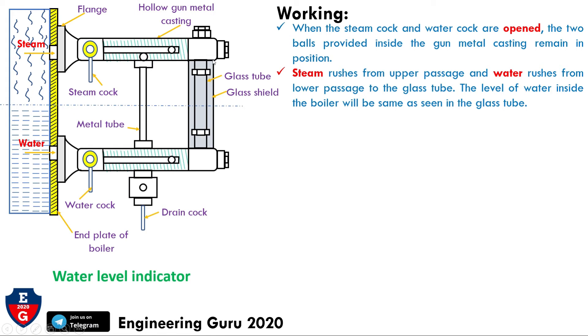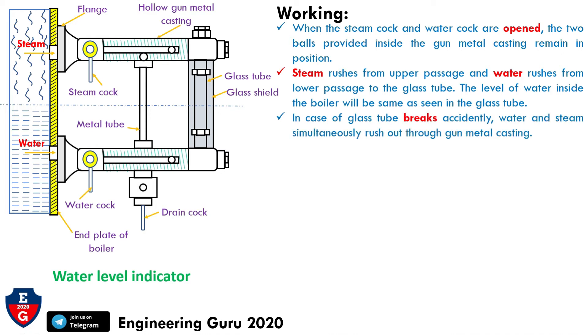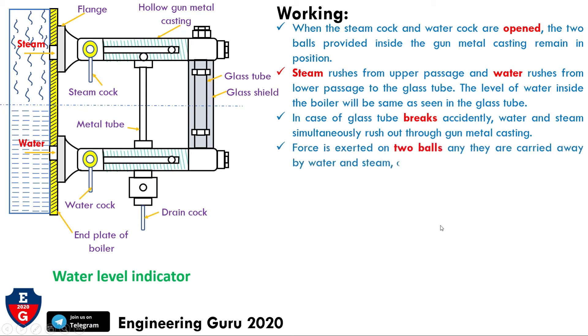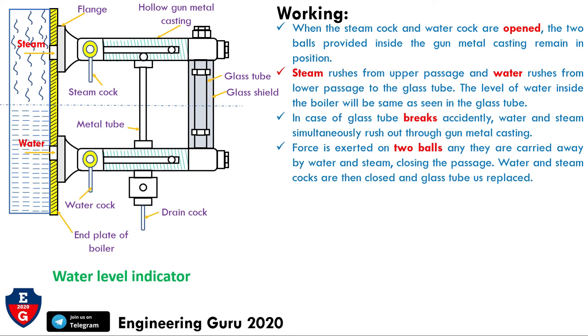The level is checked by the glass tube. In case the glass tube breaks accidentally, water and steam simultaneously rush out through the gun metal casting. A force is exerted on the two balls and they are carried away by the water and steam, closing the passages. The water and steam cocks are then closed and the glass tube is replaced. The direction of the cocks becomes horizontal when closed, and we can then replace the damaged glass tube.